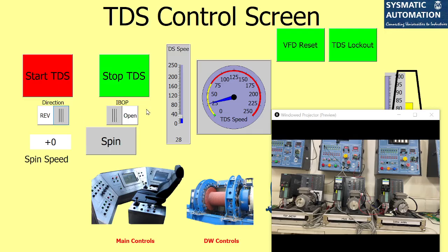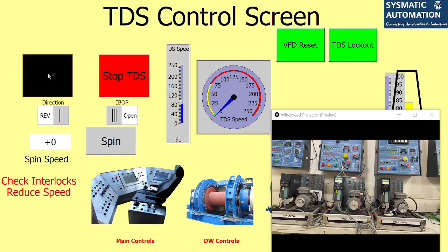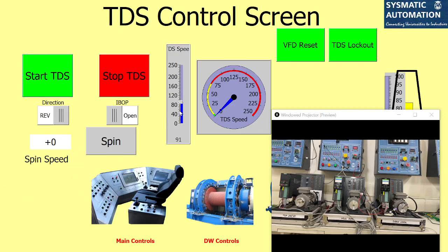There are some more interlocks here. At this stage, if I stop the top drive, keeping some speed reference at some level, and I try to start my top drive, it doesn't allow me to start. It tells me to reduce the speed. This is again an interlock. All these interlocks are programmed in my PLC. So the fault now is that I have to reduce the speed before starting the top drive. If I reduce the speed and then start, there are no alarms now, right?